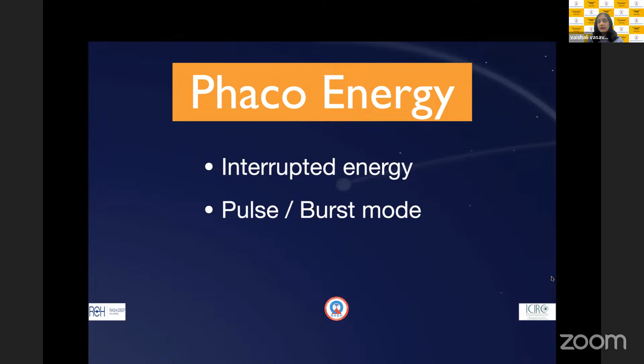The other is what we call a burst mode, which is a more refined form of the pulse mode, where you have a burst of energy, you decide, let's say 100 milliseconds, followed by a burst of off time. You can say that I want 100 milliseconds on time and 100 milliseconds off time, or 20 milliseconds off time. So these are all refinements of the same concept of using interrupted energy. And I think all of us should use interrupted energy as a rule. Continuous energy is really very harmful and detrimental, particularly when you use higher amplitude.